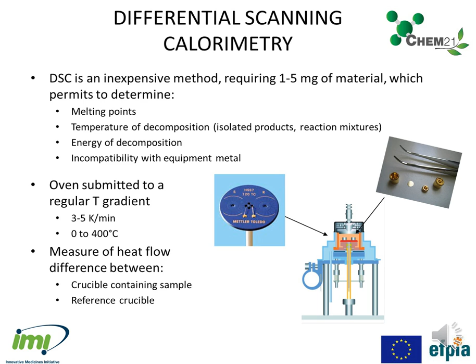The sample is introduced in a small crucible which is closed. It is introduced in the cell which also contains an identical empty crucible which serves as reference. The oven is submitted to a regular temperature gradient, usually 3 to 5 Kelvin per minute, from 0 degrees to 300 or 400 degrees. The cell contains sensors, which measure the heat flow exchange through the bottom of the crucibles, and the thermogram will plot the heat flow difference between the crucible containing the sample and the reference crucible, hence the term of differential scanning calorimetry.